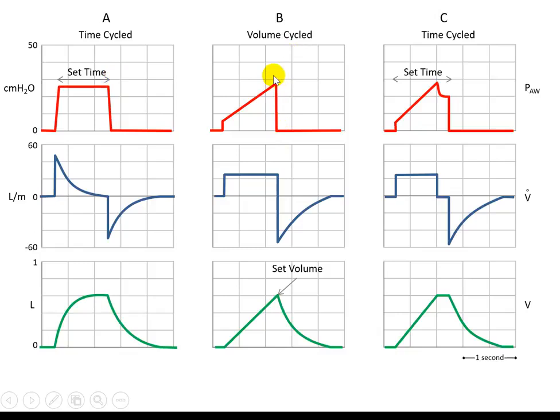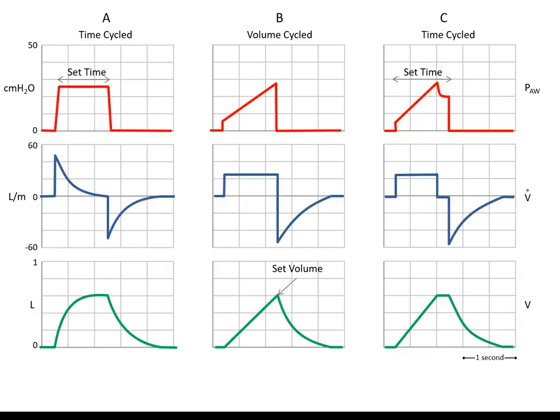When cycling by volume, once you reach a certain volume, immediately after that the pressure is released and exhalation starts. If it is set for time, you can finish the inspiratory flow and deliver the tidal volume, but the time has not elapsed yet for inspiration. That's why the breath goes into a holding period called the plateau period — the volume is inside the lung, the flow is zero, and there is a pressure required to overcome the lung and chest wall elastance.